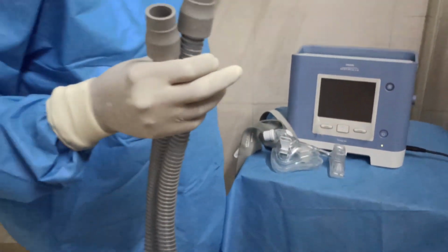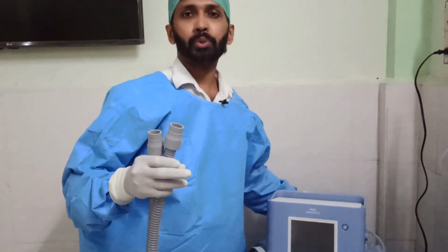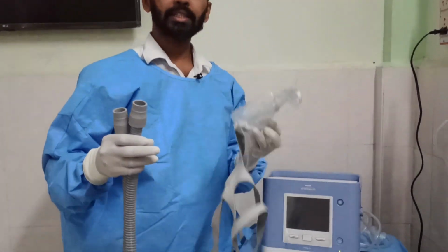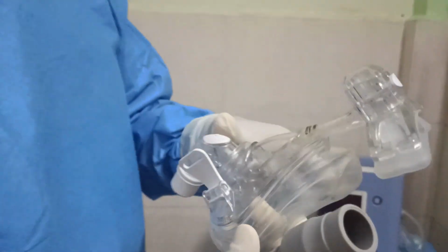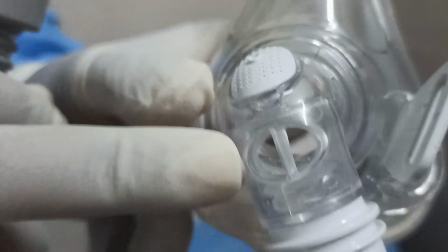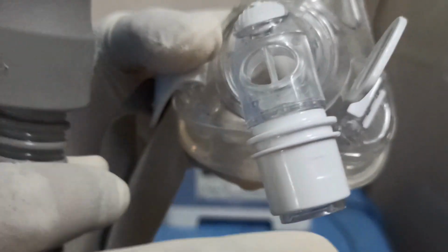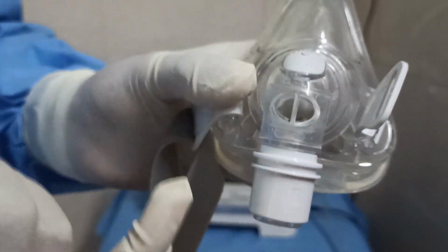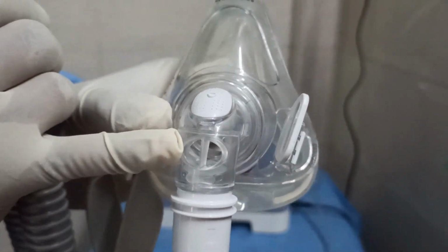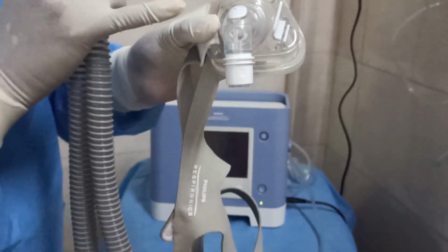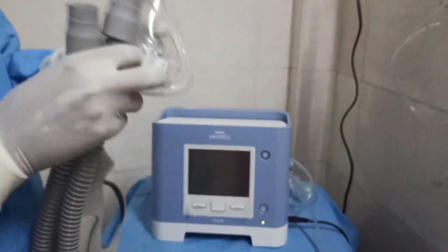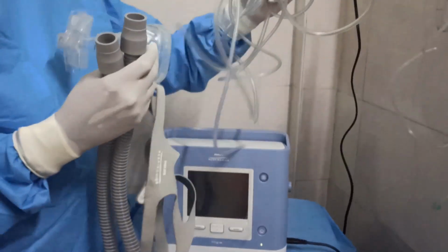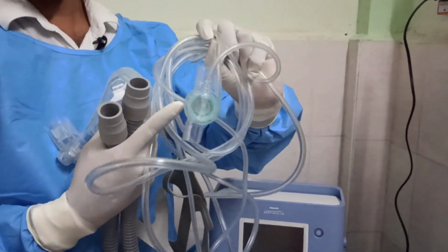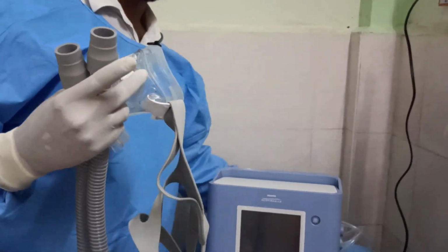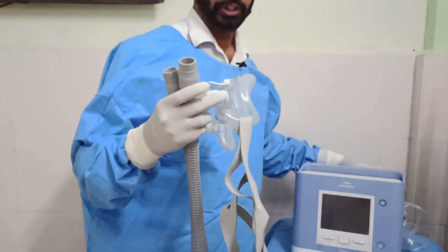At the same time, if you are using it for non-invasive ventilation, we are using a type of mask in which you can see an expiratory valve is there. That means once the patient exhales, the air comes out through this valve. So in non-invasive ventilation, the expiratory valve is here, and in invasive ventilation, we attach another tube to let the expiratory air go out. I will tell you how to use both invasive and non-invasive ventilation.